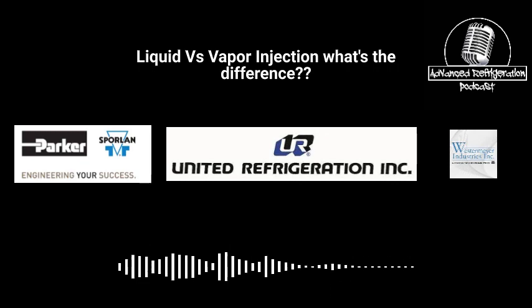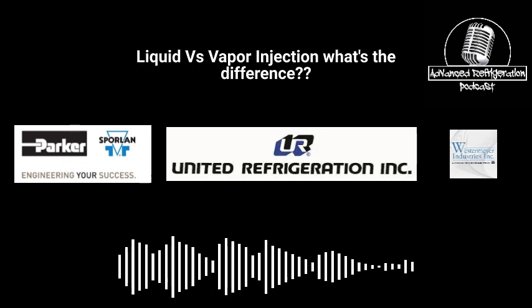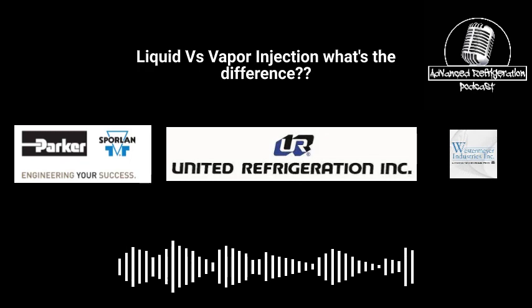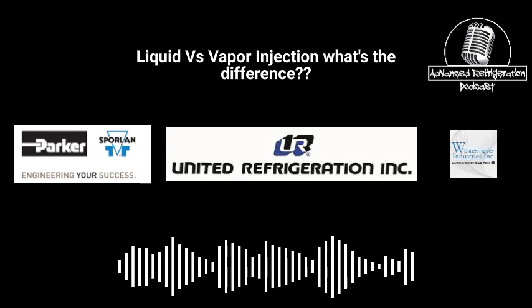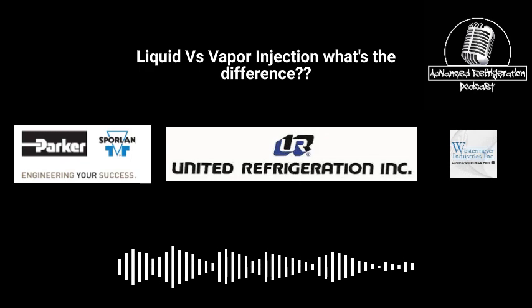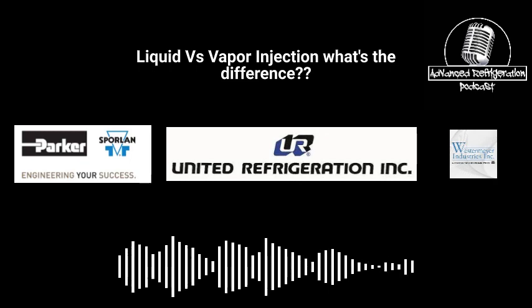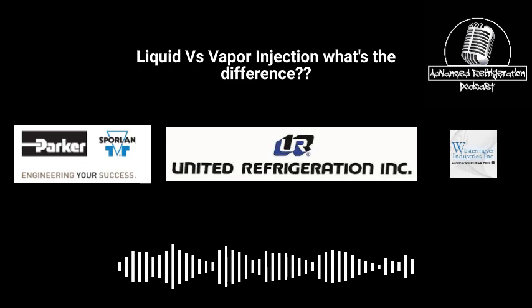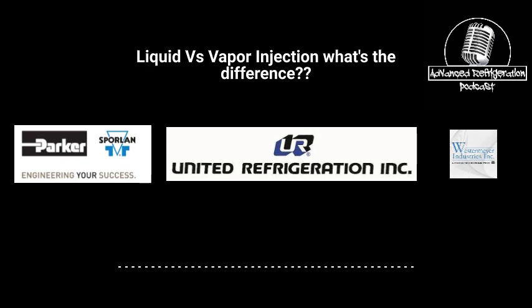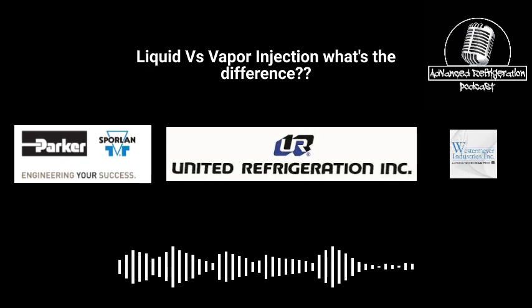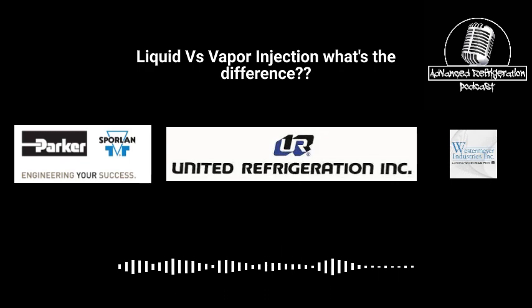So I found this out physically because someone that I was with was trying to rebuild a vapor injection solenoid without isolating the compressor, because they thought, hey, if I get it down to about 10 psi on the suction, I should have 10 psi on that vapor injection line out of that compressor. That is a big negative. When this person went to rebuild that solenoid, they had like 50 or 60 or 70 pounds on there pushing against that solenoid.